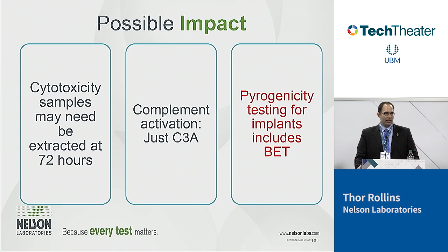But in this document, and there's been another guidance document released for orthopedics, the FDA is requiring all implants to have LAL testing done on them. So no matter where you're located, if you're considered an implant, the FDA wants you to do a bacterial endotoxin or an LAL test on that implant. And this is a big impact to the orthopedic industry. The LAL test is cheap and quick. It's not the test, it's the samples. These orthopedic samples are not cheap, and they take a long time to manufacture. So now we have to submit more samples for testing. So this was a big impact to the orthopedic industry as far as pyrogenicity.